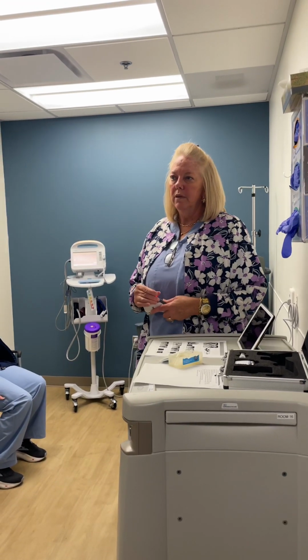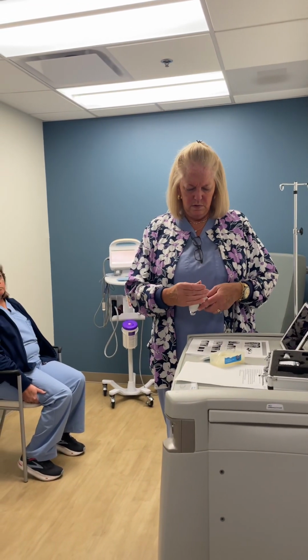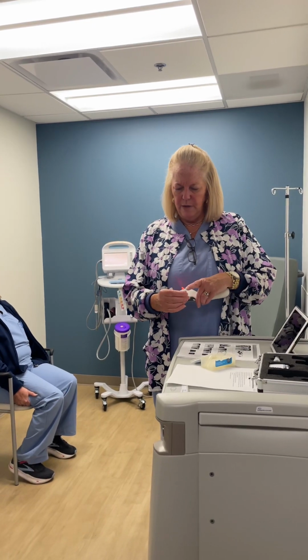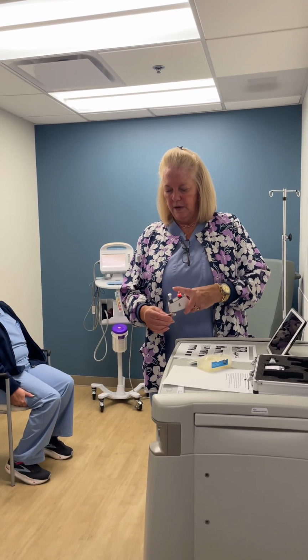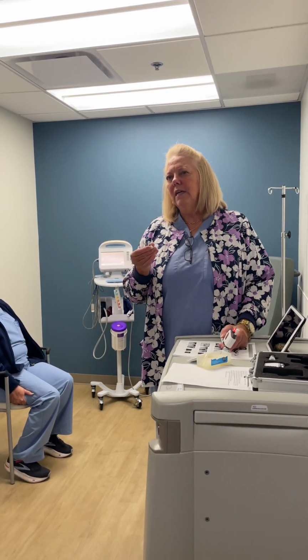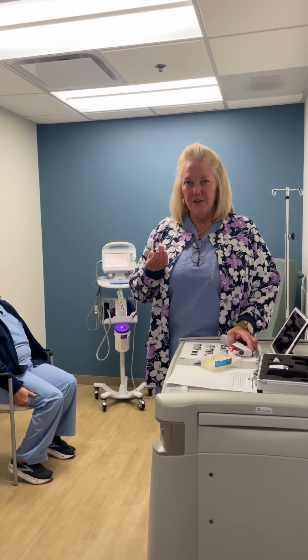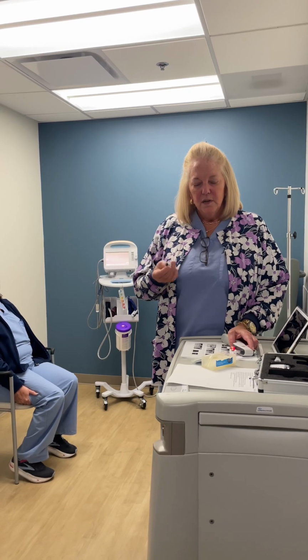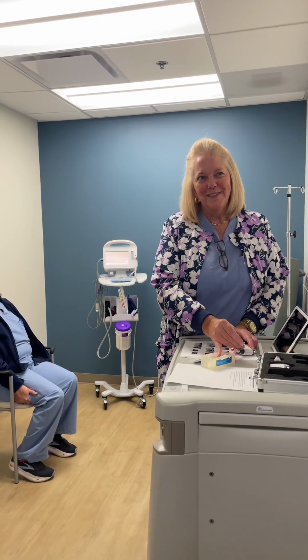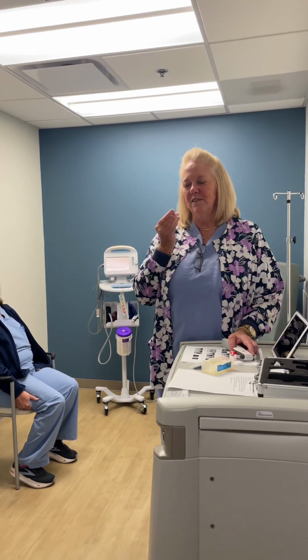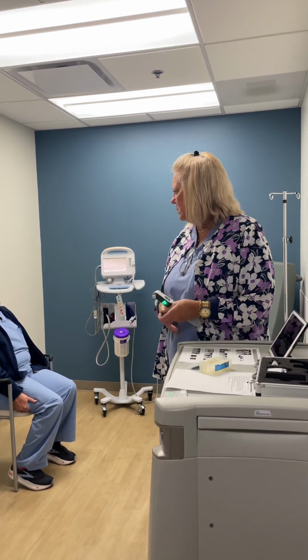It gets cleaned with alcohol, any part that touches the probe here. Also, a lot of times, because we use the gel, the gel is still on the patient's eye even though you flush it. So it'll cause this little probe to stick to their eye, and then it sucks the gel back in. So then a lot of times you have to take the probe out and clean it. It'll just keep giving you an error message.